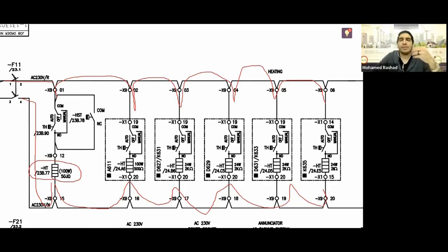What is this heater used for? It's used in case you have humidity or moisture inside your panel, so it doesn't accumulate on the wires. The temperature of the cells inside must be kept above a certain level to prevent the presence of humidity, so I raise the temperature to prevent that.